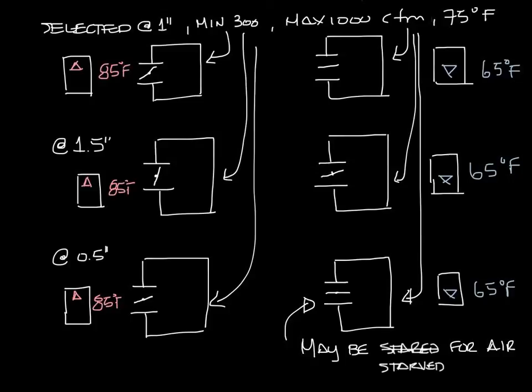The only way to really do this is to go through the controller and specifically tell the box to drive the damper open and closed. So now you know why the minimum and maximum CFMs on a VAV box don't always equate to full closed and full open.